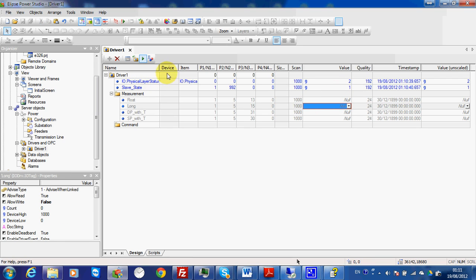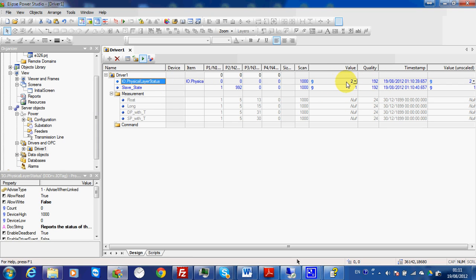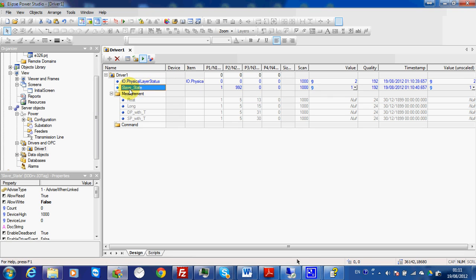The physical layer state tag has nothing specifically to do with IEC 104 — it is a common tag for all protocols in our kit that you can use to check if communication between two drivers is working. The slave state tag, on the other hand, is a specific tag for IEC 104 that you can also use to verify the connection.